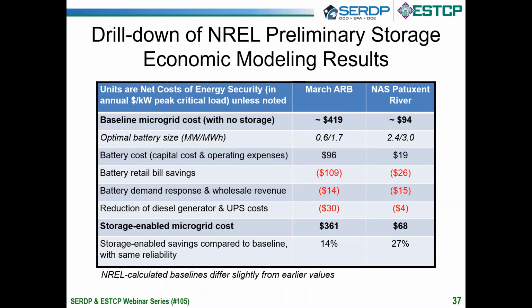So these are mid-sized to somewhat large batteries for commercial and industrial customers. The cost of adding the batteries is $96 per kilowatt of peak critical load per year at March, and $19 at Patuxent River, where the battery cost gets spread over a much, much larger critical load. Then you can see the savings farther below in the chart. Demand response and wholesale revenue at Patuxent River almost pays entirely for the battery: $15 per kilowatt per year in new revenues versus a $19 cost for the battery system.